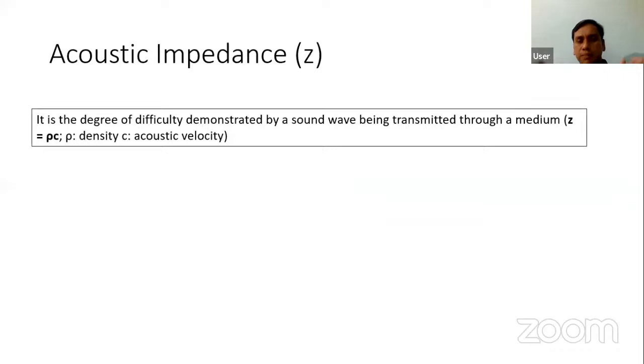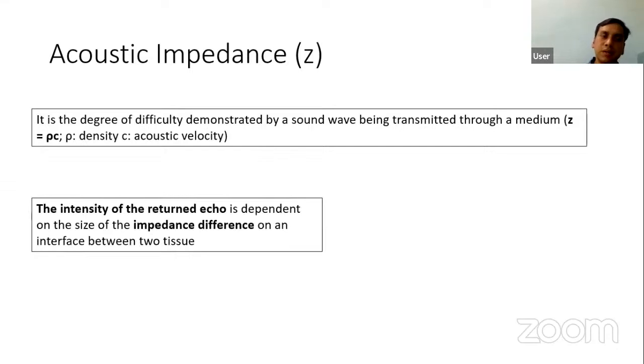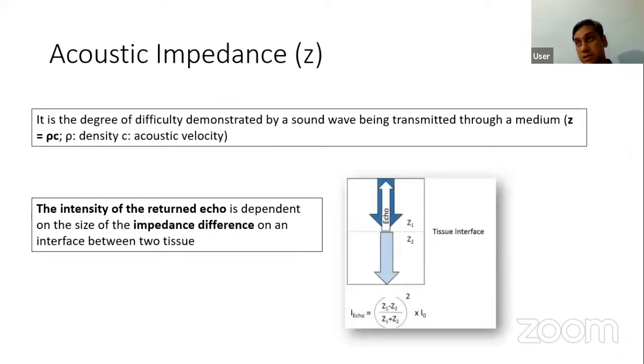Now, acoustic impedance is a very important parameter because it has a lot of clinical importance. It is defined as the degree of difficulty demonstrated by a sound wave being transmitted through a medium. You can calculate it by multiplying the density of the medium with the speed at which the sound wave passes through this medium. So it depends upon the density. The clinical importance is that the image created by the ultrasound depends upon the returned echo, that's the returned wave. And the intensity of this returned echo is dependent on the size of the impedance difference between two tissues. As the sound wave hits, because there are multiple tissues in the body, there are interfaces.